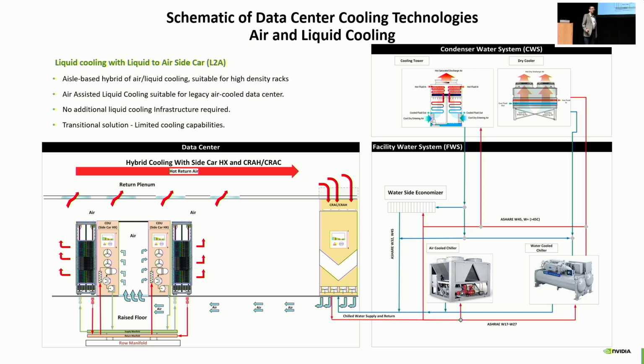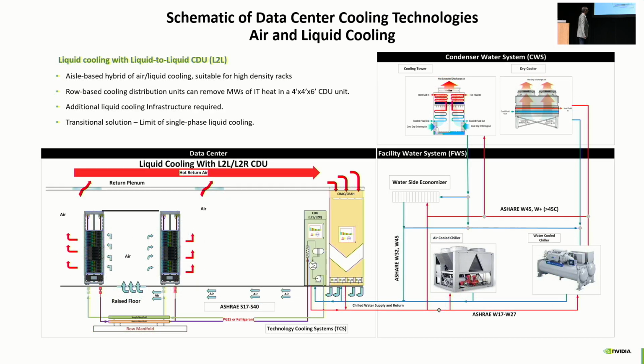And these sidecars can today remove maybe about 100 kilowatts, 120, 130 kilowatts of heat from a rack. Not that much, but it's speed of light. We can use them instantly today. So we can bring racks with liquid cooling, use sidecars, and with no changes to the infrastructure it basically becomes 100% air cooling. Within the rack, you have liquid cooling, with a sidecar that produces liquid inside of that rack. And that's how we remove heat today in a data center. Remember that the right side remains the same. There's no change to that.